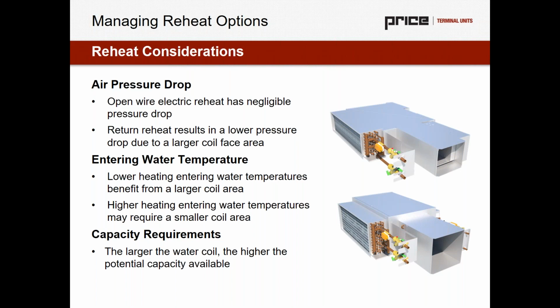So I've had projects as low as 100 degrees for reheat, which is very, very low and tends to be a bit of a design hurdle to get the heating capacity required. But with that large return coil, even with a 1 or a 2 row option, we're going to see the ability to provide a significant amount of heating capacity for those exterior zones within the design.